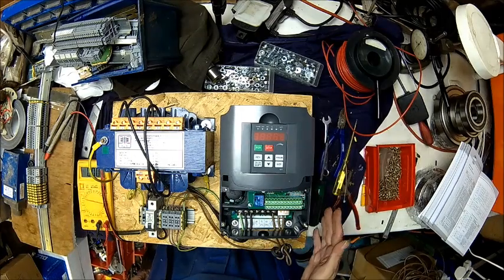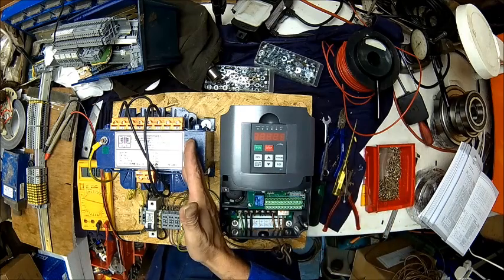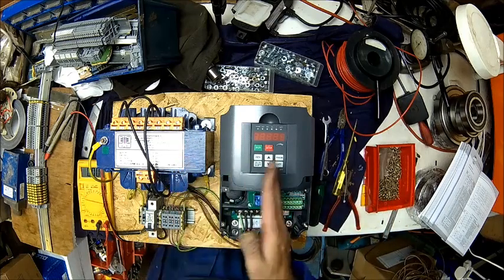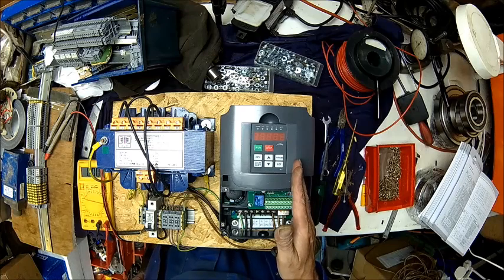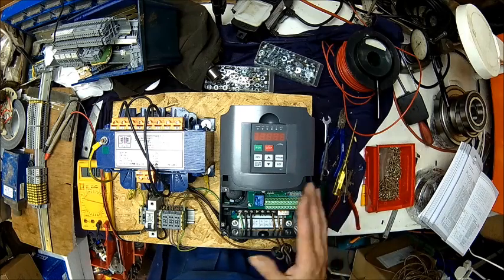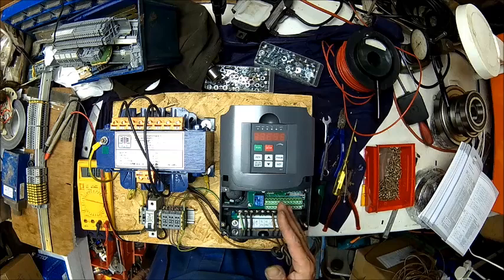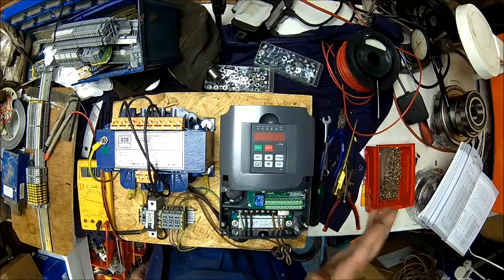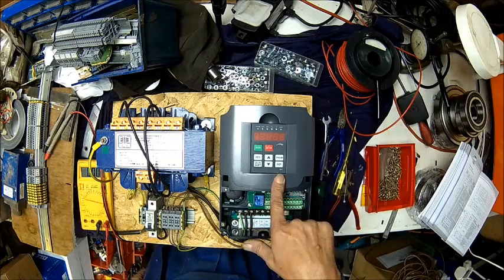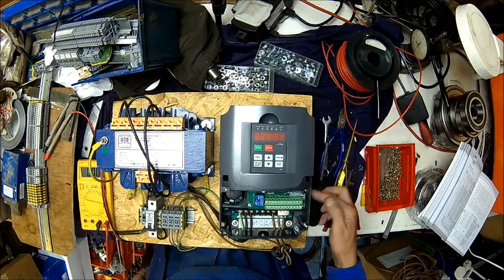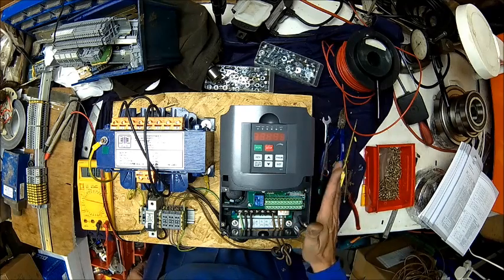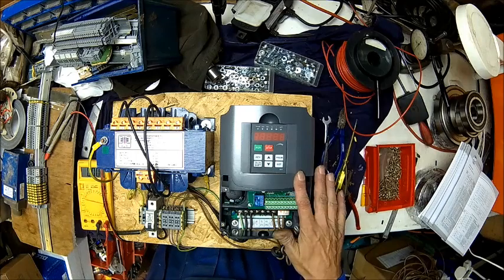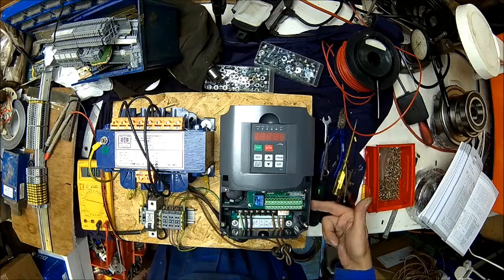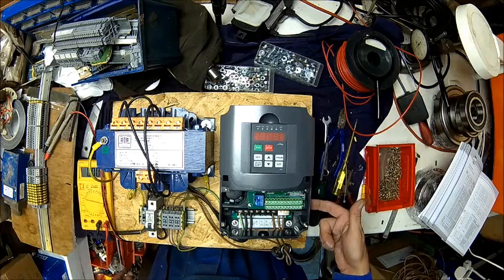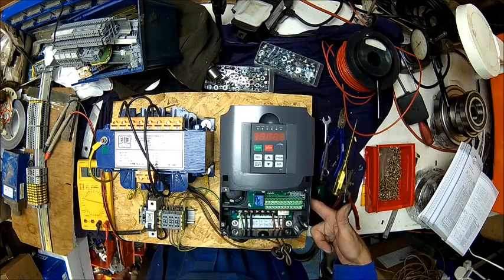This setup works pretty much for any voltage. It doesn't matter what the input voltage is, as long as it's higher, or at least equal, or a little bit higher than what you need. So if you've got a 208 volt 60 Hertz motor, set that thing to 60 Hertz, 208 volts. Make sure the current rating of the inverter, which is on the nameplate, is good enough for your motor. If you go lower in voltage, this thing will not have 4 kilowatts. At 208 volt it may have probably in the region of 2 kilowatts, because it has only 8.5 amps.